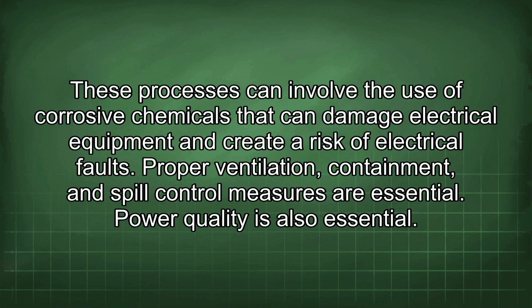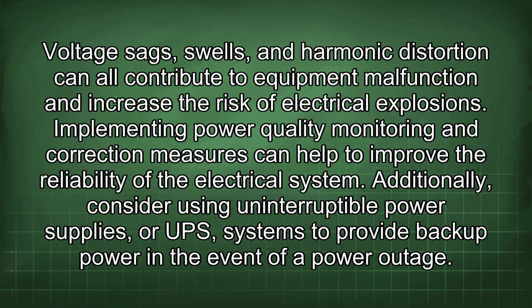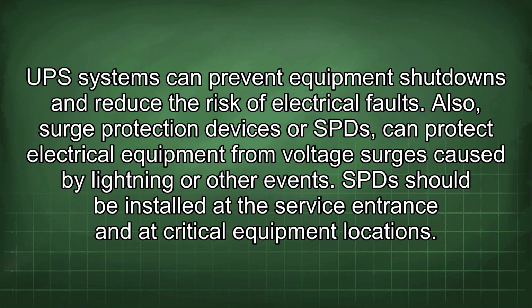Power quality is also essential. Voltage sags, swells, and harmonic distortion can all contribute to equipment malfunction and increase the risk of electrical explosions. Implementing power quality monitoring and correction measures can help to improve the reliability of the electrical system. Additionally, consider using uninterruptible power supplies, or UPS systems, to provide backup power in the event of a power outage. UPS systems can prevent equipment shutdowns and reduce the risk of electrical faults.